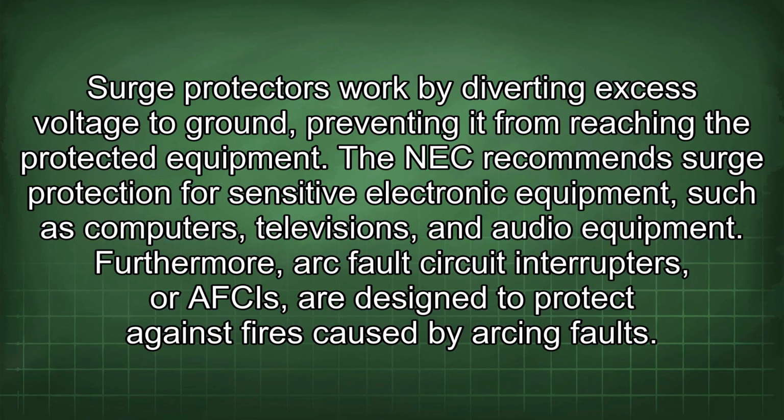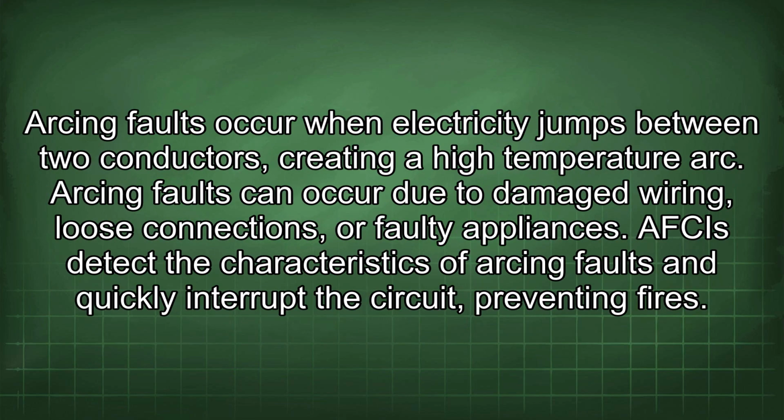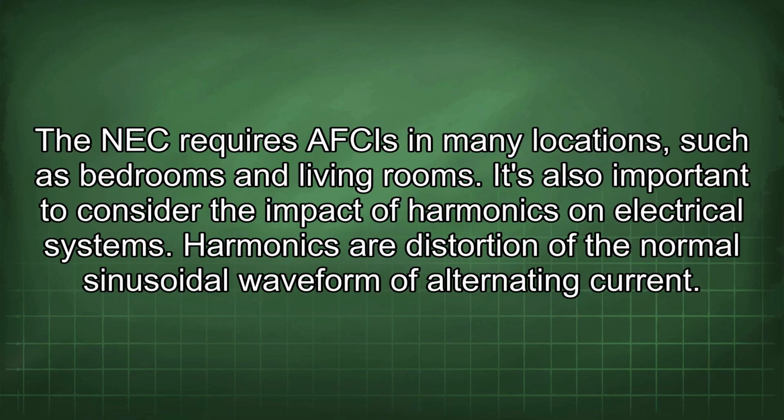Furthermore, arc fault circuit interrupters, or AFCIs, are designed to protect against fires caused by arcing faults. Arcing faults occur when electricity jumps between two conductors, creating a high-temperature arc. Arcing faults can occur due to damaged wiring, loose connections, or faulty appliances. AFCIs detect the characteristics of arcing faults and quickly interrupt the circuit, preventing fires. The NEC requires AFCIs in many locations, such as bedrooms and living rooms.